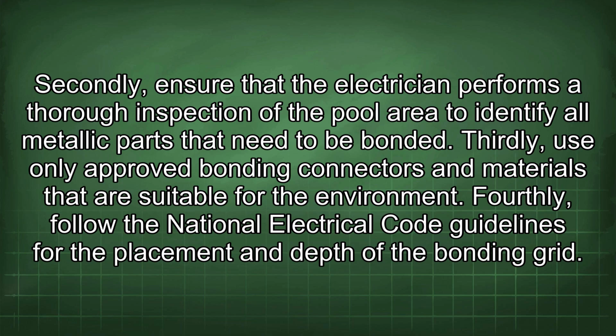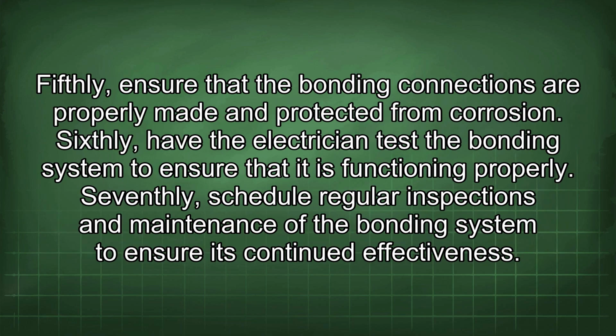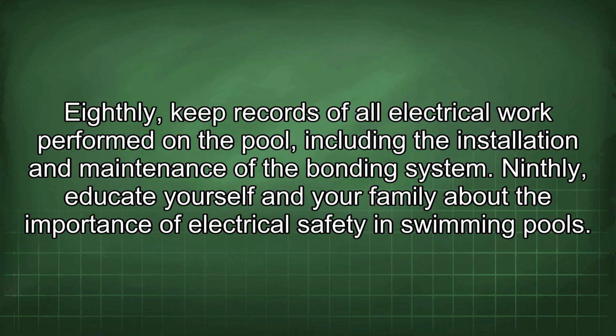Thirdly, use only approved bonding connectors and materials that are suitable for the environment. Fourthly, follow the National Electrical Code guidelines for the placement and depth of the bonding grid. Fifthly, ensure that the bonding connections are properly made and protected from corrosion. Sixthly, have the electrician test the bonding system to ensure that it is functioning properly. Seventhly, schedule regular inspections and maintenance of the bonding system to ensure its continued effectiveness. Eighthly, keep records of all electrical work performed in the pool, including the installation and maintenance of the bonding system.